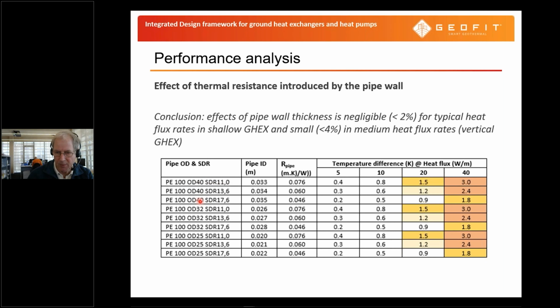Here we have a 40 millimeter type and the wall thickness is 40 divided by 17.6. So a thinner wall, and here a thicker wall. You get the pipe internal diameter, and then we get here the thermal resistance of the pipe wall material itself. And that varies, of course, depending on the diameter, 25, 32, or 40 millimeters, and the thickness of the wall.